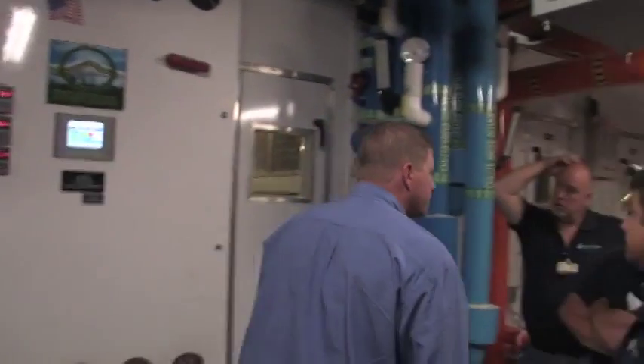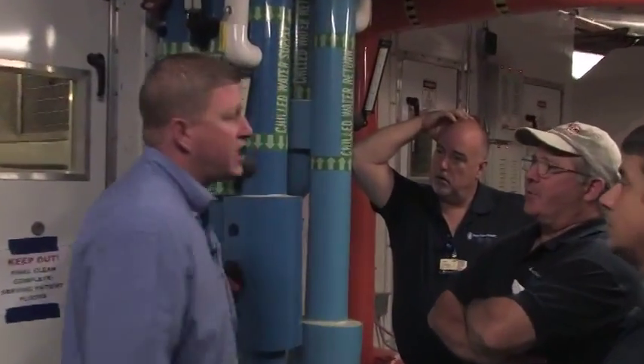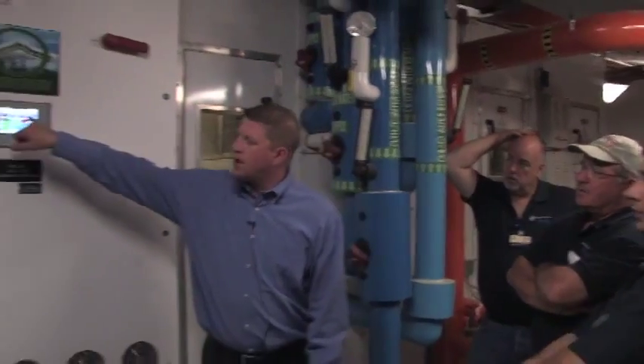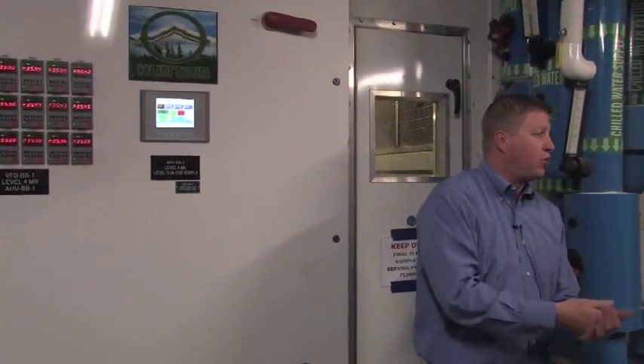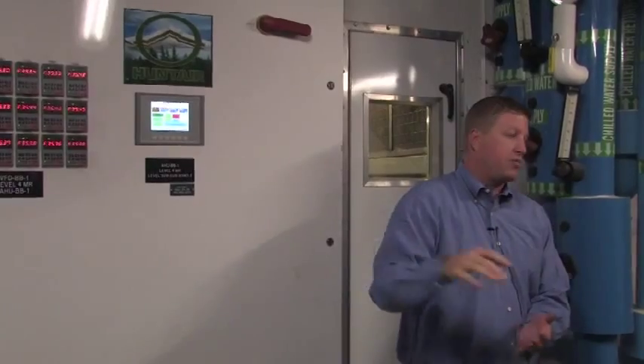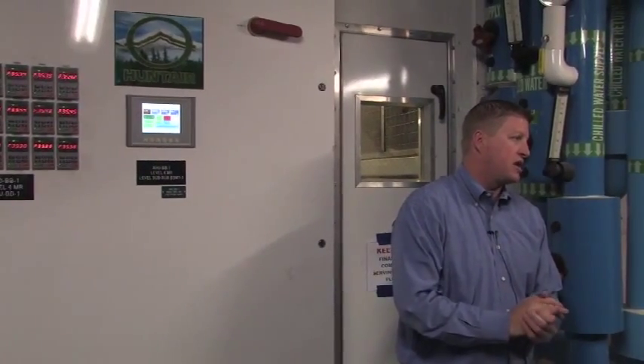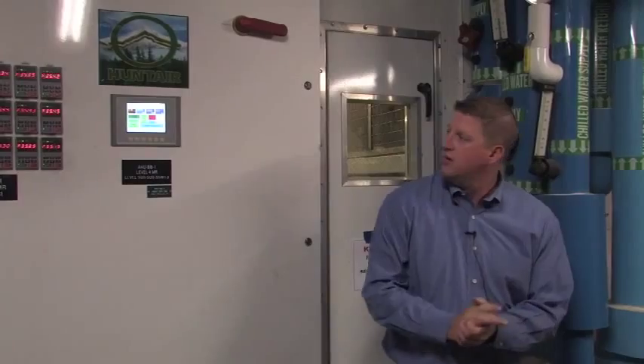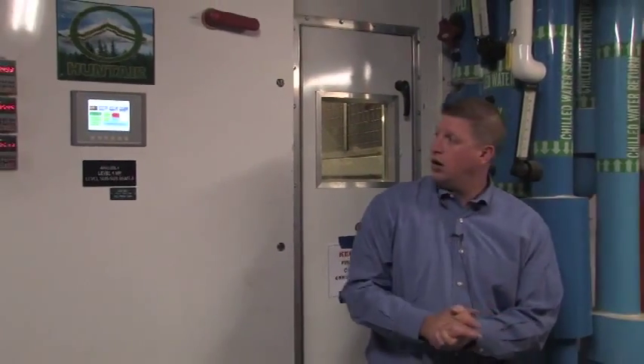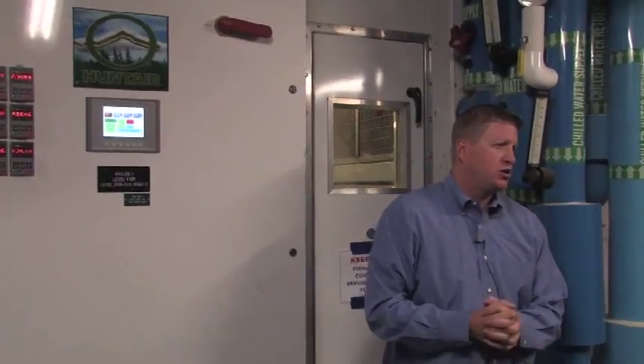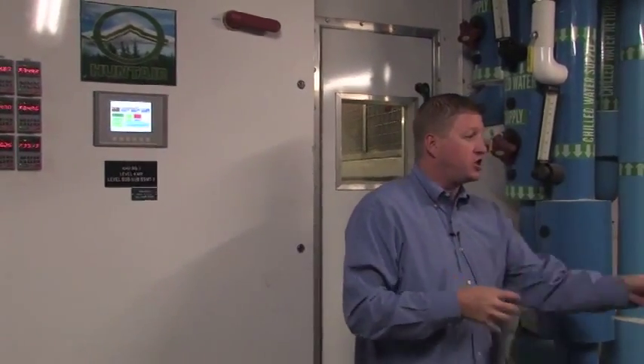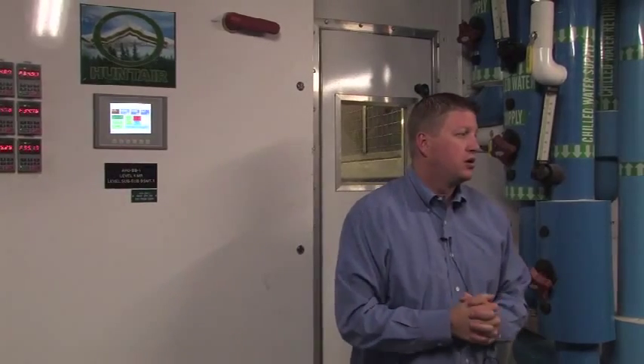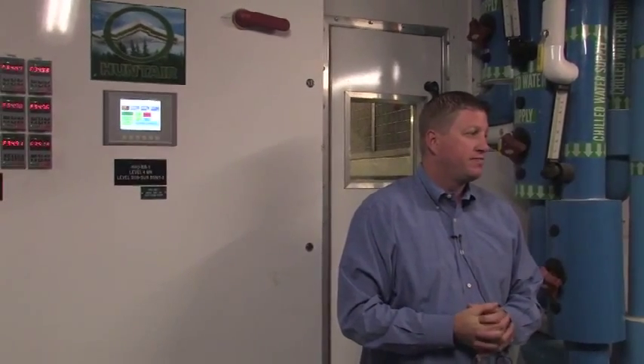What's that, sorry? Static set. What's typical static? So this is the total static pressure. E&E, your set point is a different number. That would be through E&E. You'd have to talk to them. I don't know what it is. My guess is it's probably not that high by the looks of where we're at right now. No, we're low. Yeah. You're probably set at about 1 inch. That's the total of the fans. Your set point's just down in the ductwork. You know what I mean?